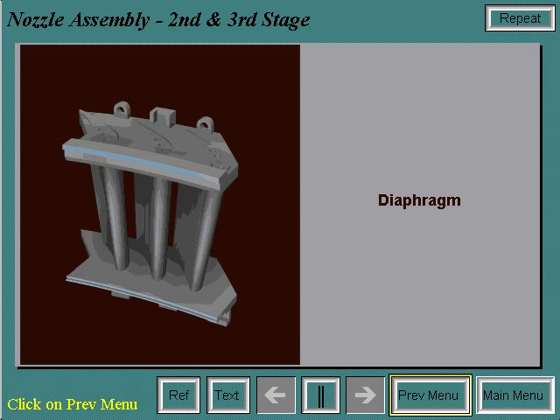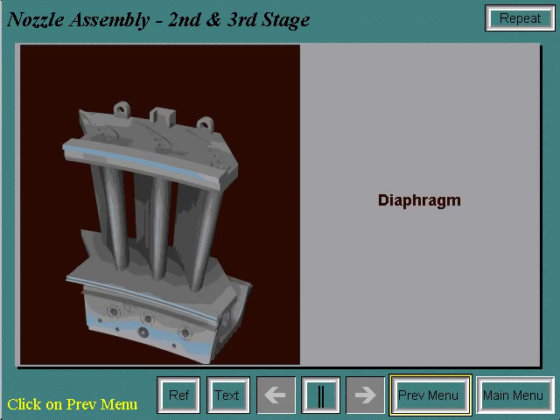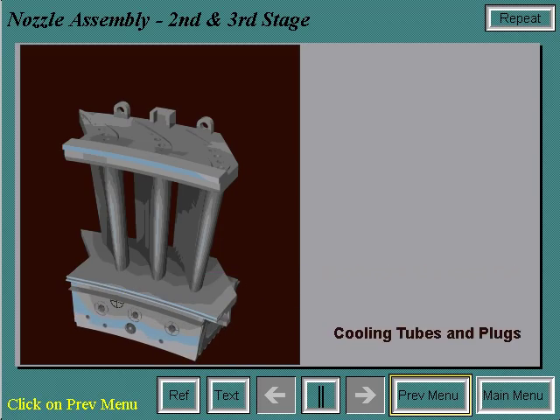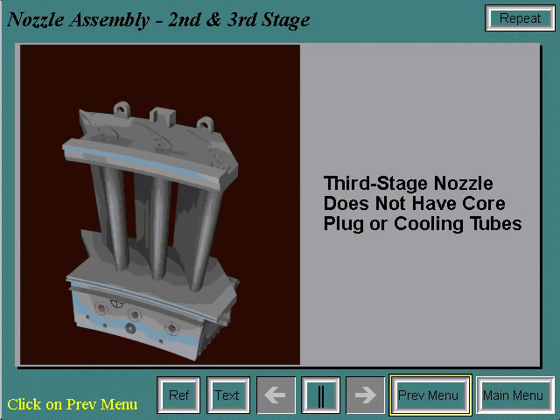The diaphragm section is then attached and a pin is installed for nozzle to diaphragm alignment. Wheel space cooling tubes and plugs are installed in the diaphragm. The third stage nozzle is similar to the second stage nozzle but it is not forced air cooled, so there is no core plug and there are no cooling tubes.